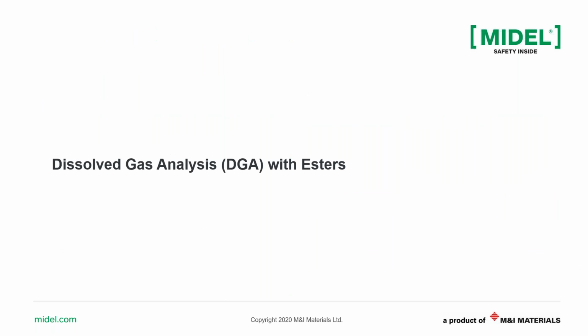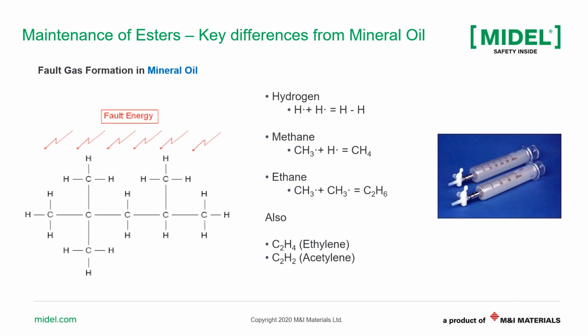Now we go to how we assess a transformer filled with an ester through a DGA, because DGA is one of the main tools we use to spot faults in a transformer. And again, we need to emphasize the difference in chemistry. Esters have different chemical structure than mineral oil. Now, in front of you, we start with mineral oil. It's a hydrocarbon, so any fault will decompose this liquid to produce gases, DGA gases, such as hydrogen, methane, ethane, ethylene, and acetylene. This is for mineral oil.